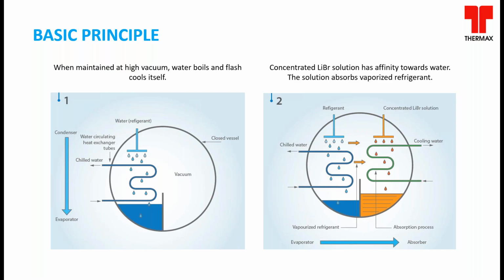When you can evaporate water at 3 to 4 degrees Celsius, you can cool the chilled water to a temperature close to 5 to 7 degrees Celsius. Now, the chilled water getting cooled in the evaporator of the absorption chiller can be taken to various applications. It can be process cooling, air conditioning, or various other cooling requirements. Now, as we have seen, we have generated the refrigerant vapor. Since we are operating under vacuum, when the vapor gets generated, it increases the pressure, reducing the vacuum level. So we have to maintain vacuum levels constant so that this refrigerant can evaporate at constant temperatures, delivering chilled water.